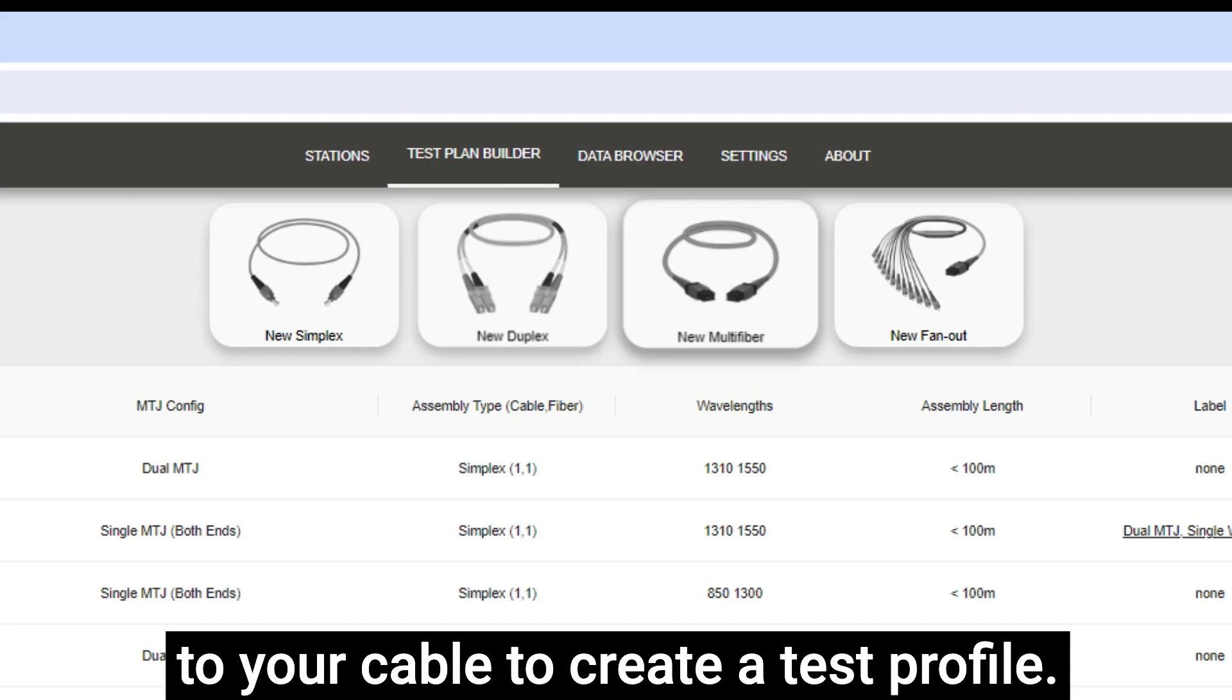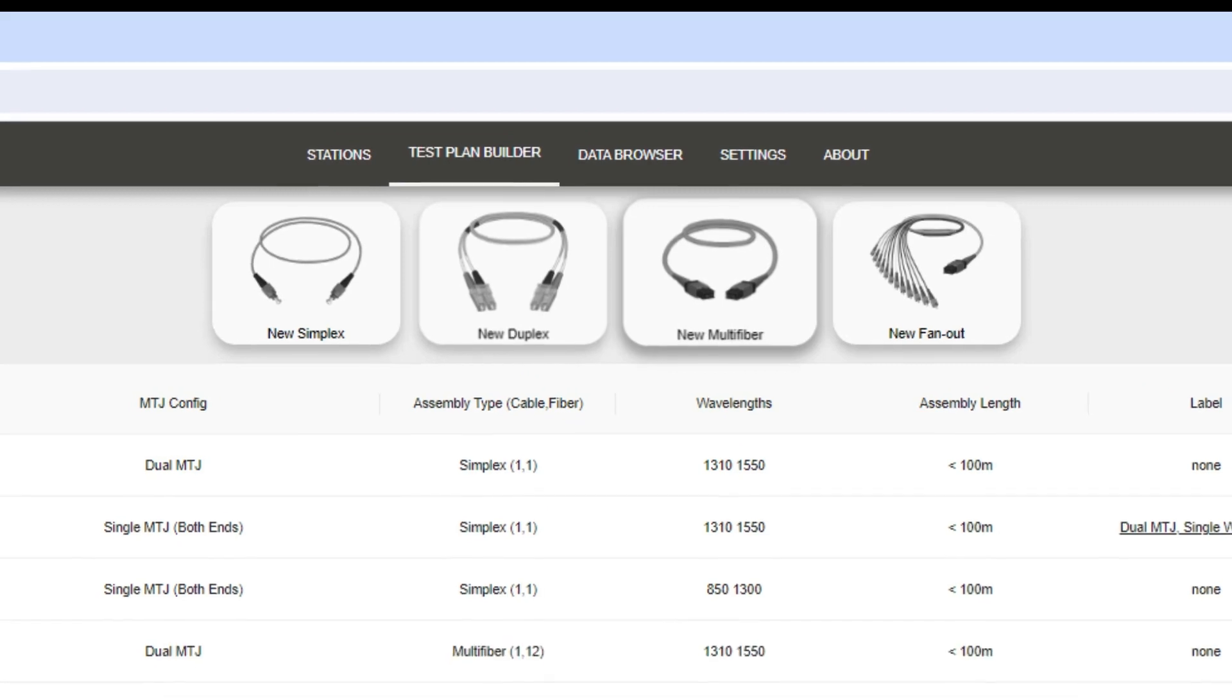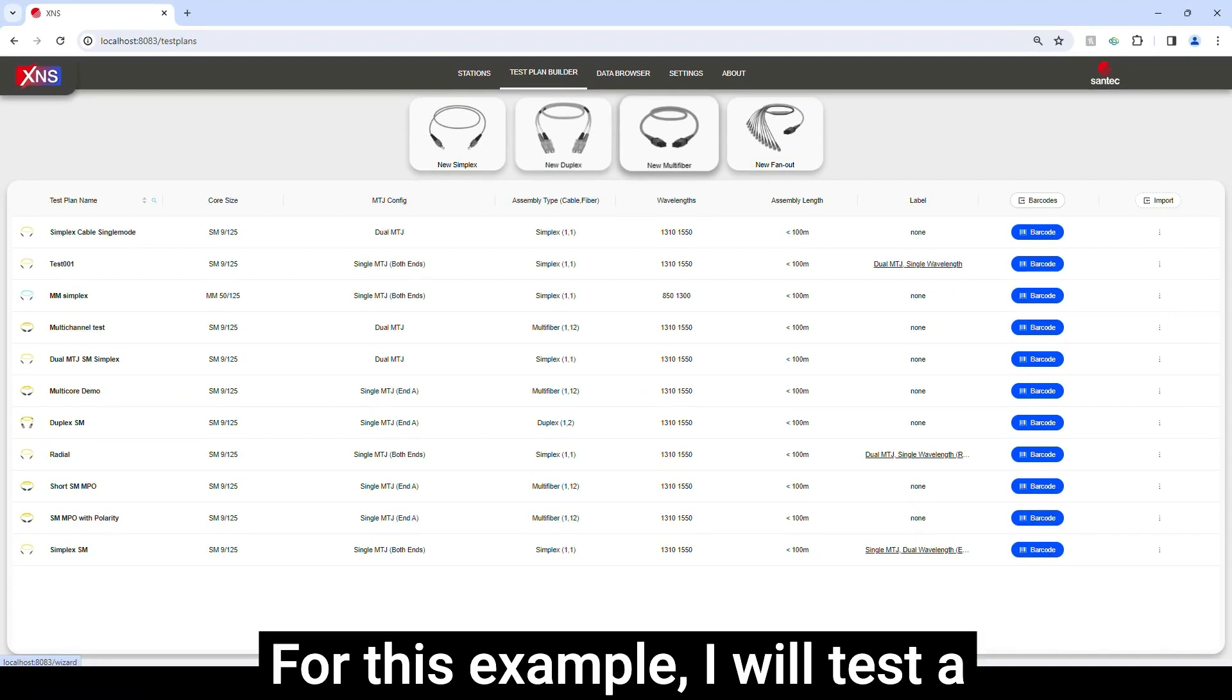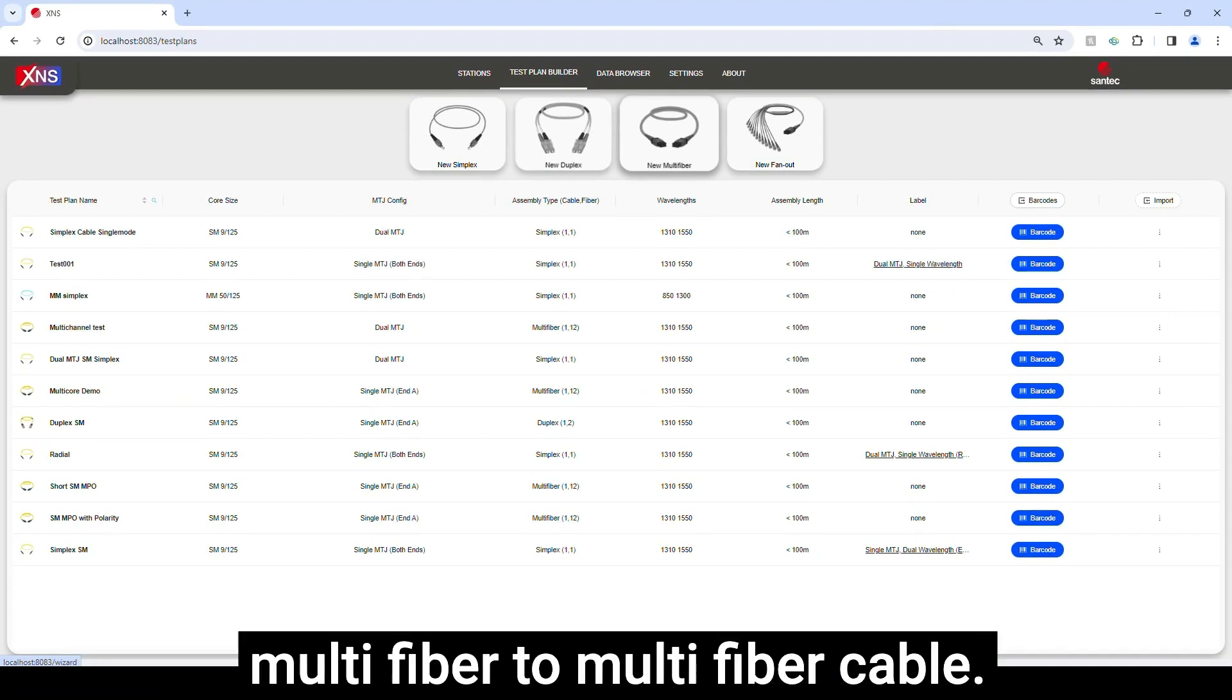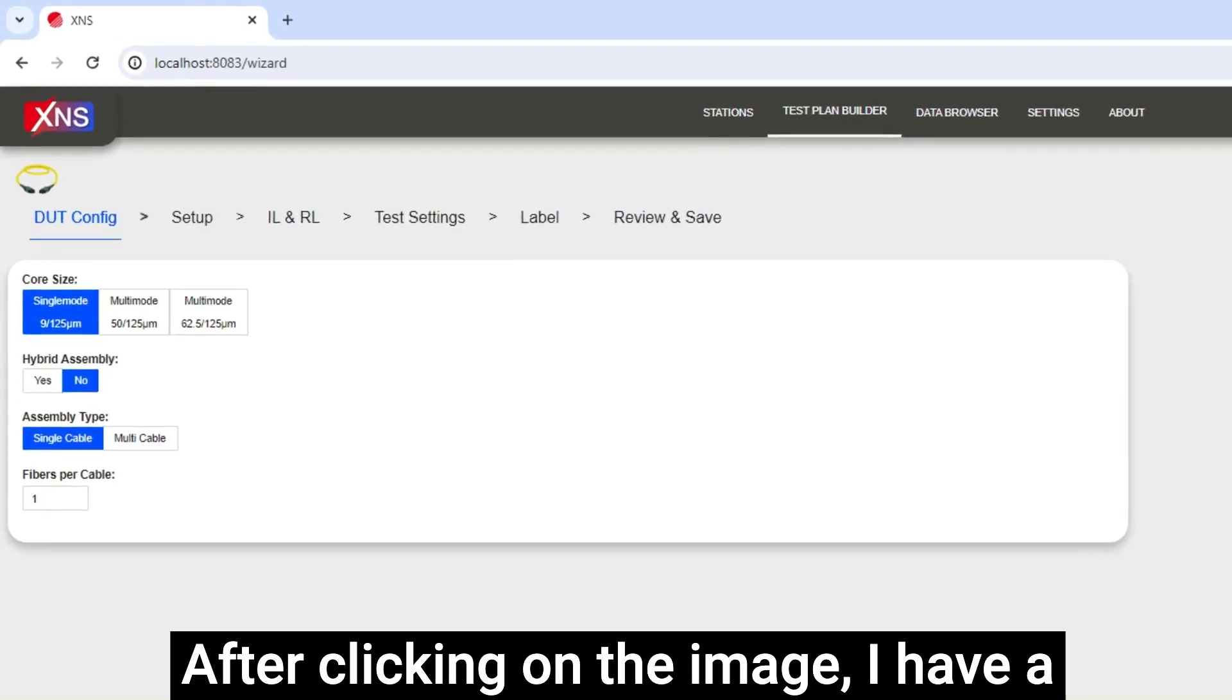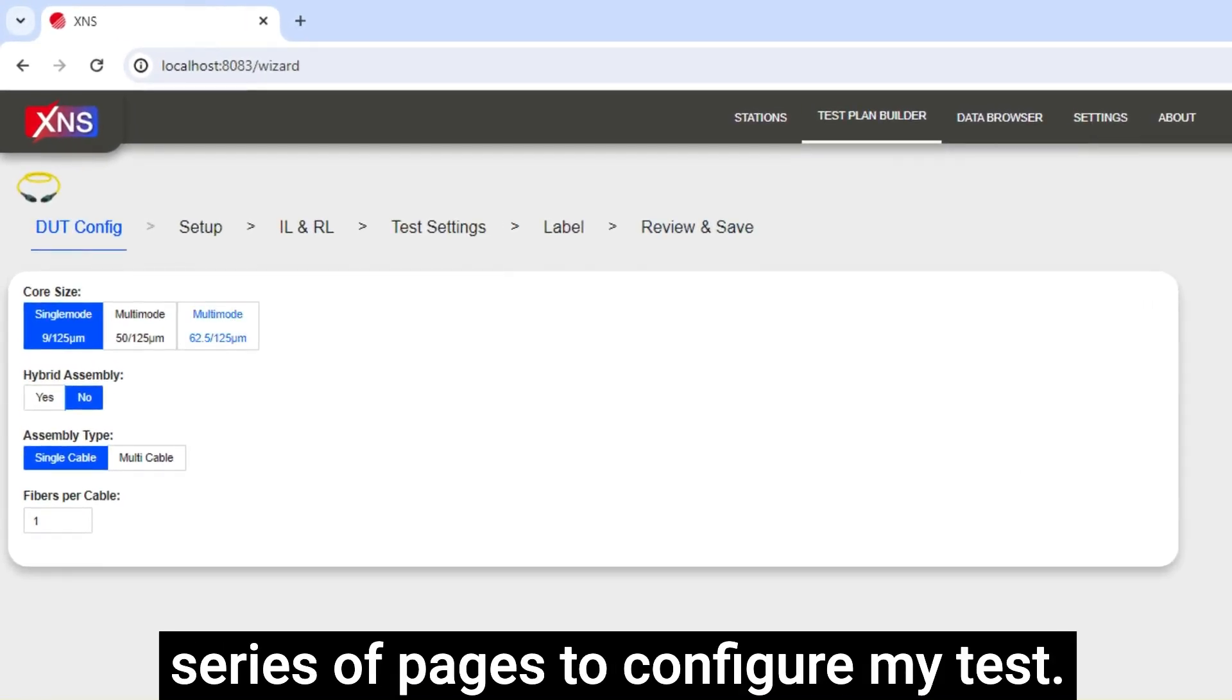Click on the image that corresponds to your cable to create a test profile. For this example I will test a multi-fiber to multi-fiber cable. After clicking on the image I have a series of pages to configure my test.